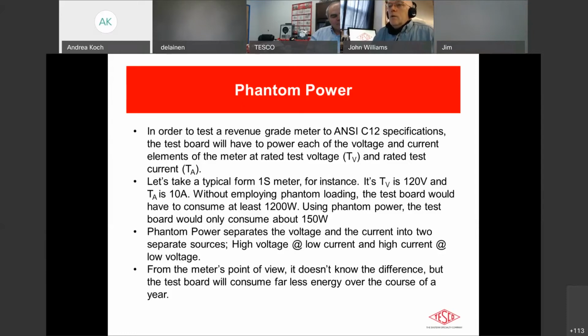And why do we do that? In order to test a revenue grade meter, for example, to the ANSI C12 specifications, we have to test test volts and test amps. A simple example would be a 1S meter. You have 120 volts, you have a TA of 10 amps, let's say. Without employing phantom loading, the test board would have to consume 1200 watts just to test that 1 meter. But if you created the energy for the meter using phantom power, the test board would only consume 150 watts.